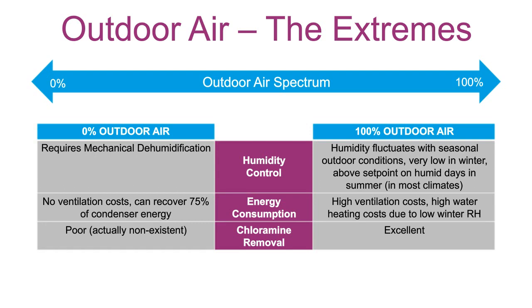On the flip side, at 100% fresh air, the humidity would fluctuate in a very wide range, very, very low in winter and above set point on humid days in summer in almost all climates except the mountain regions. Because the outside air is going to have a pretty major effect on what goes on. Your ventilation costs would be very high, and also your water heating costs would get quite high because you would drive the humidity down so low during the winter time that the evaporation rate would increase actually by over 100% if you run it that way. Chloramine removal, on the other hand, would be excellent. You would have people thinking that space felt very fresh.